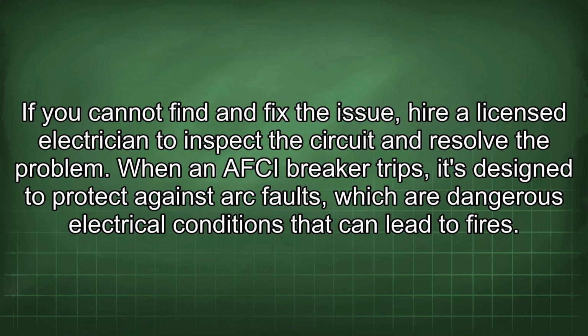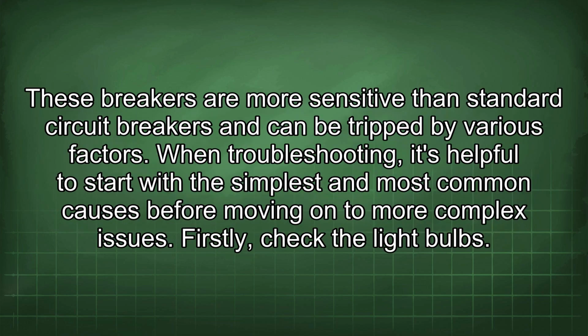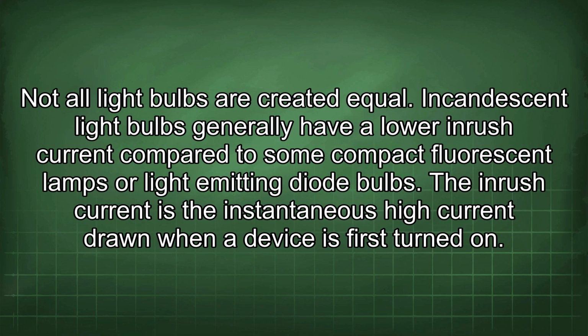When an AFCI breaker trips, it's designed to protect against arc faults, which are dangerous electrical conditions that can lead to fires. These breakers are more sensitive than standard circuit breakers and can be tripped by various factors. When troubleshooting, it's helpful to start with the simplest and most common causes before moving on to more complex issues. Firstly, check the light bulbs. Not all light bulbs are created equal.